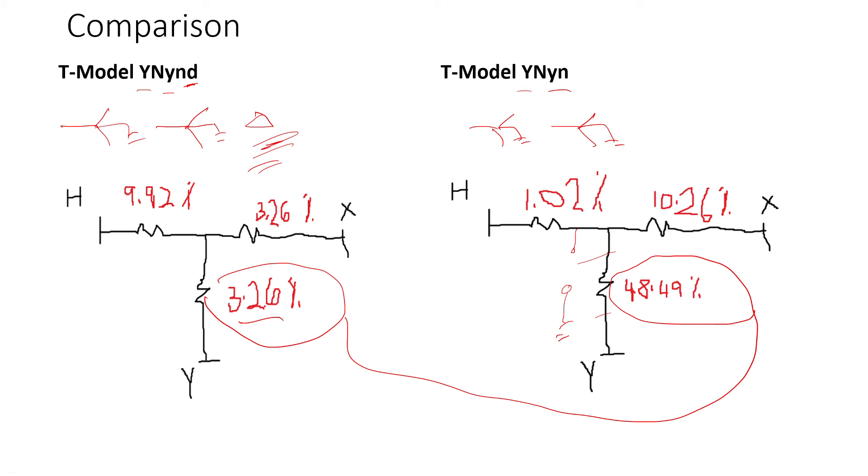So that's one conclusion. Keep in mind when you take these two and you sum them up, it should be very close to the positive sequence impedance. So the sum of these two, that's one.